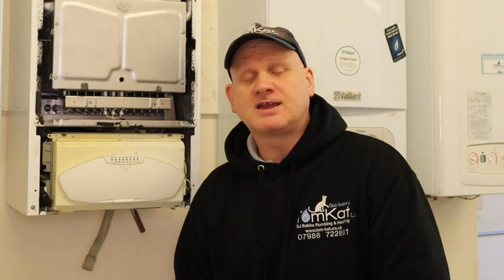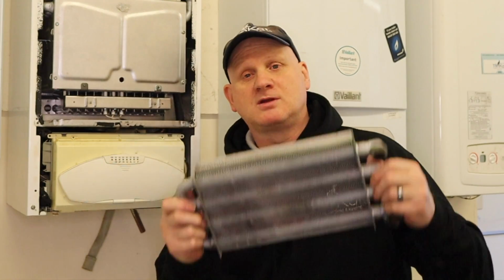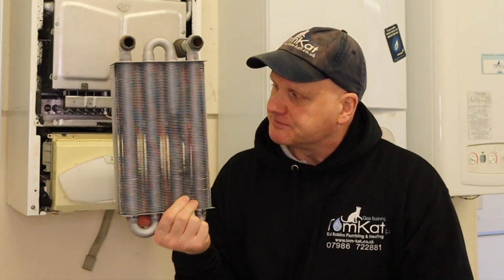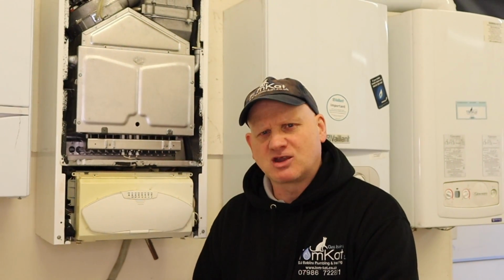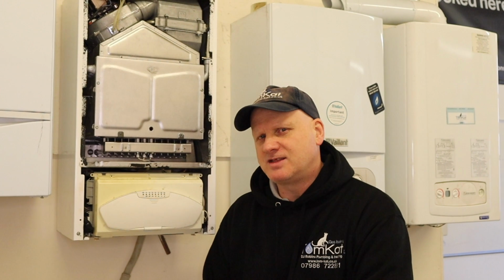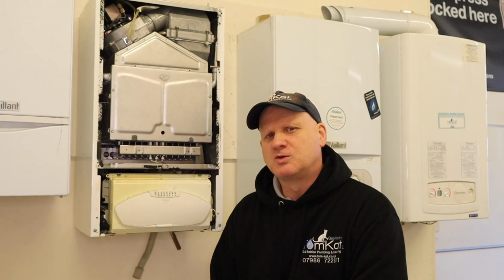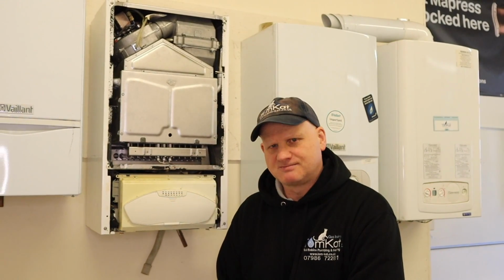Now, after the cast iron heat exchanger, we went to this type of heat exchanger. So this is a copper heat exchanger. I know it's silver, it's coated in a special coating, but this actually is all copper. Now, it is said that the thermal conductivity of copper is 20 times greater than stainless steel. So why aren't we using copper now as heat exchangers if they're that good? Well, again, like cast iron heat exchangers, copper isn't very good with products of combustion that are acidic.